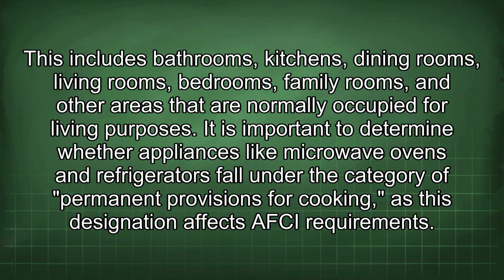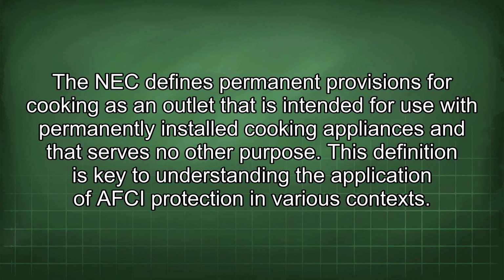purposes. It is important to determine whether appliances like microwave ovens and refrigerators fall under the category of permanent provisions for cooking, as this designation affects AFCI requirements. The NEC defines permanent provisions for cooking as an outlet that is intended for use with permanently installed cooking appliances and that serves no other purpose. This definition is key to understanding the application of AFCI protection in various contexts.